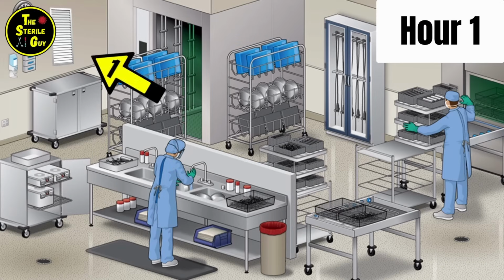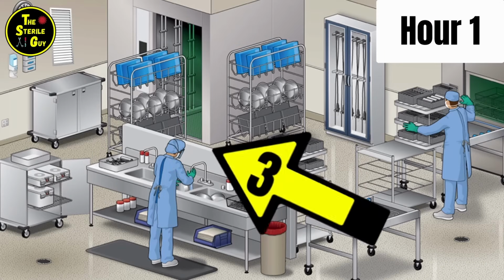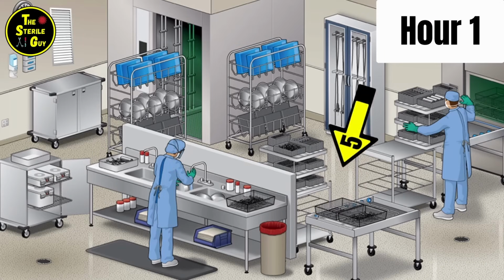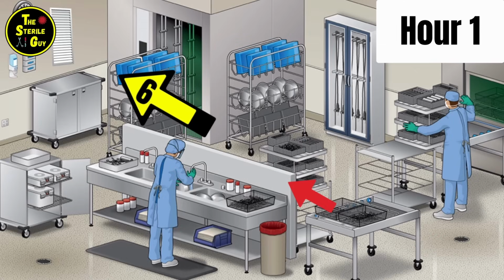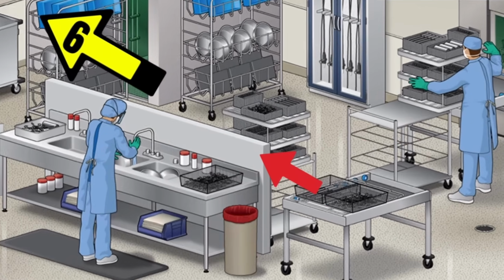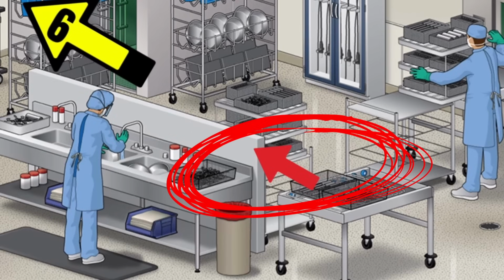Now, with the dirty area in decontamination, it works a little differently. In decontamination, more air is removed through the return vents than is actually supplied to the room from the air supply vents. What happens is, since the room doesn't have enough air to give to the return vent because the air supply is so stingy, the return vent creates this negative pressure as it pulls air from anywhere else it can. And this extra air mainly enters the room through the exposed area, usually from cracks around the doors to the room.